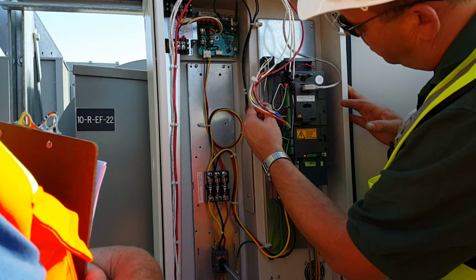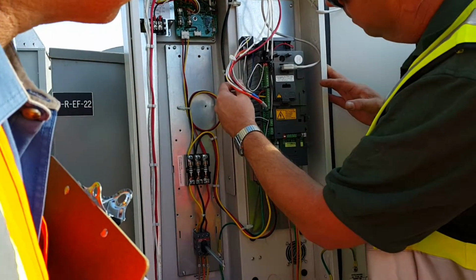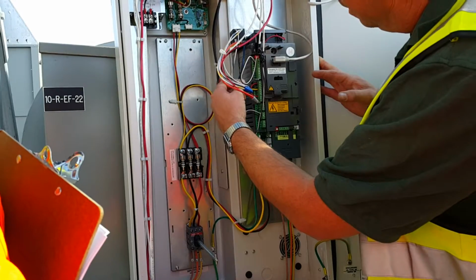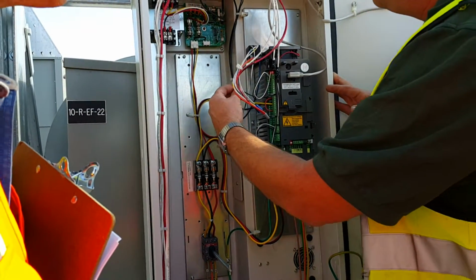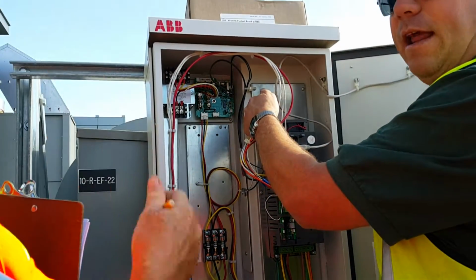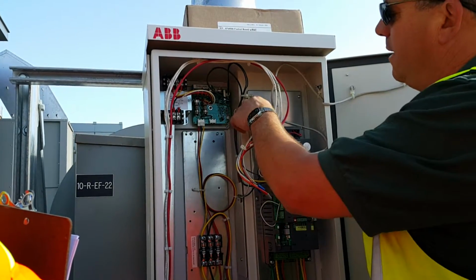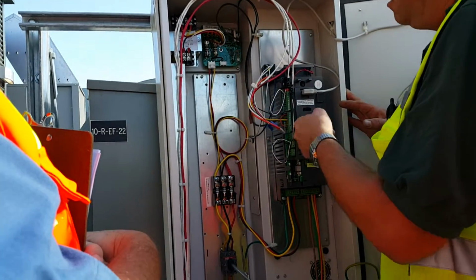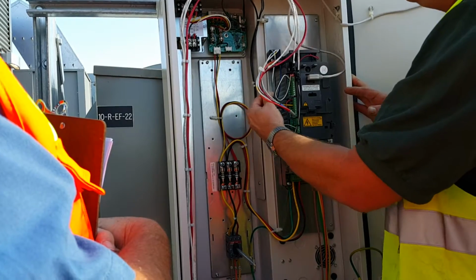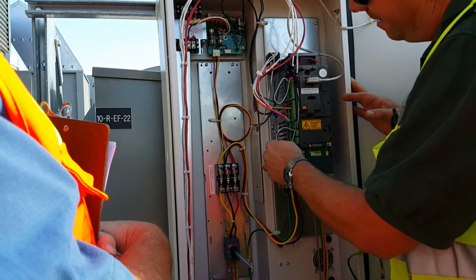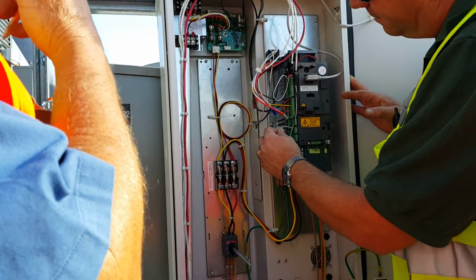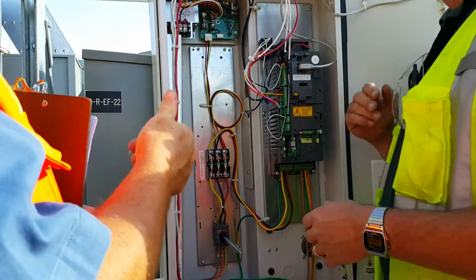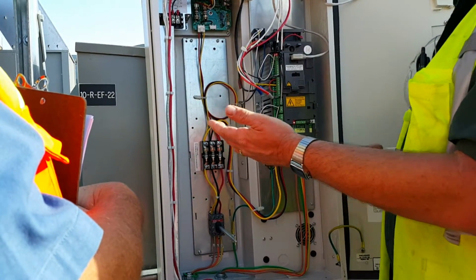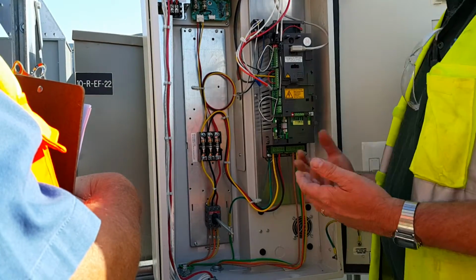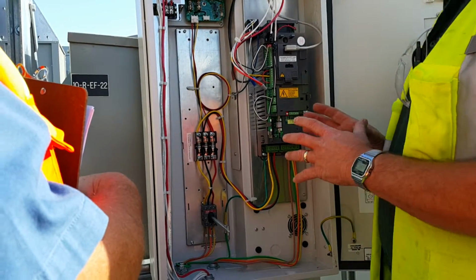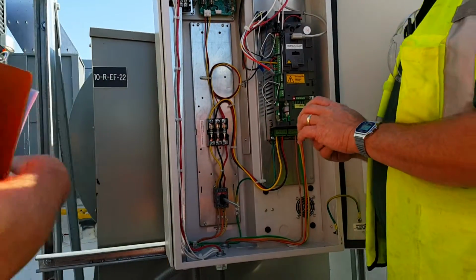And then this one and this one right here, that is your start command, okay? 24 volts, digital input 1. And the control guys are putting in a relay over here with a light and everything. So they're bringing 24 volts here, closing it, and then closing our contacts here. That's your ignition switch. And then finally, you've got a run status here. This goes back to the BMS system, and tells it, they're telling it, yeah, I'm telling you to run, are you actually running? So it sees those things together. Pretty simple control logic: start, stop, speed.